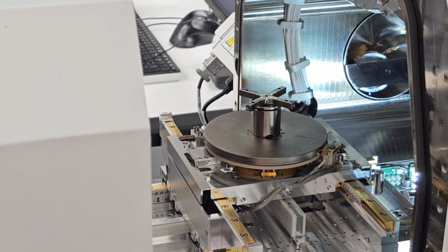The next step is to mount your sample. Now, the height of your sample is very, very important. The pole piece, which I mentioned a few minutes ago, you do not want to hit. It's very easy to damage and very expensive to replace. So whatever sample you put in here, you are always going to want to measure the height of the sample using the height measure and make sure that you are underneath that projection.